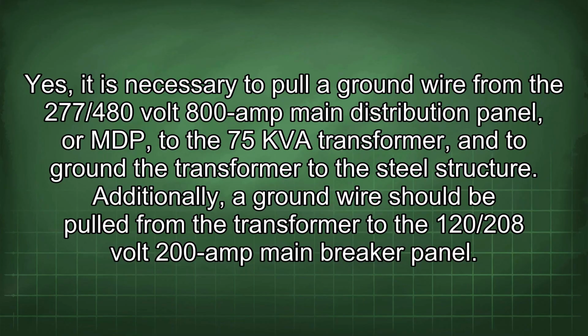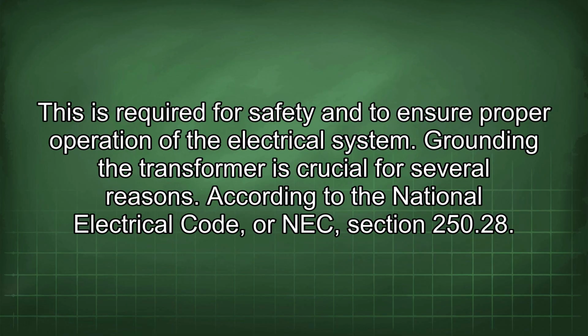Yes, it is necessary to pull the ground wire from the 277/480 volts 800 amp main distribution panel, or MDP, to the 75 kVA transformer, and to ground the transformer to the steel structure. Additionally, a ground wire should be pulled from the transformer to the 120/208 volt 200 amp main breaker panel. This is required for safety and to ensure proper operation of the electrical system.